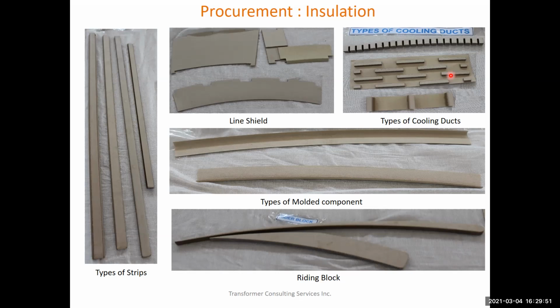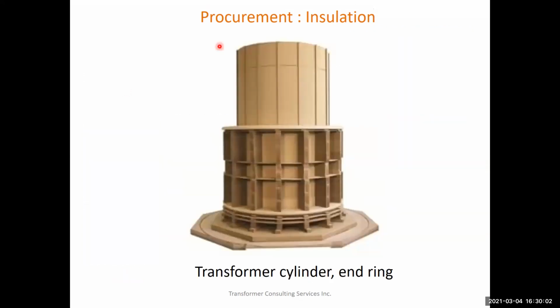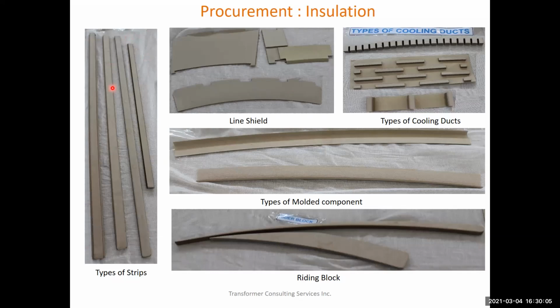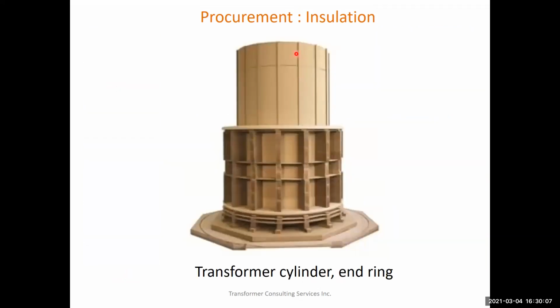So a month ago, one of my transformers failed the factory acceptance test. The failure is because of the duct stick, which I'll show you in the next picture. Here you see this duct stick is being glued to the cylinder. When it was glued, the glue was not applied properly, so the glue had a bubble inside it. When the dielectric test was done, that bubble broke down and created partial discharge.